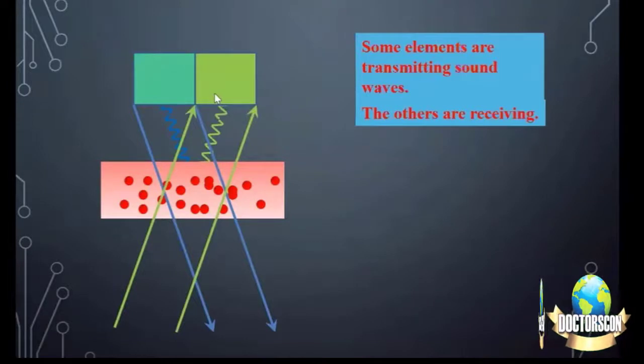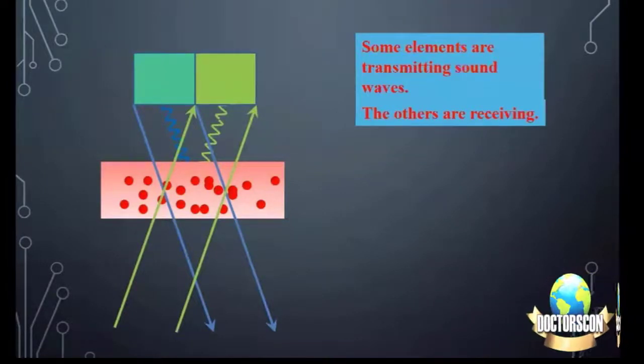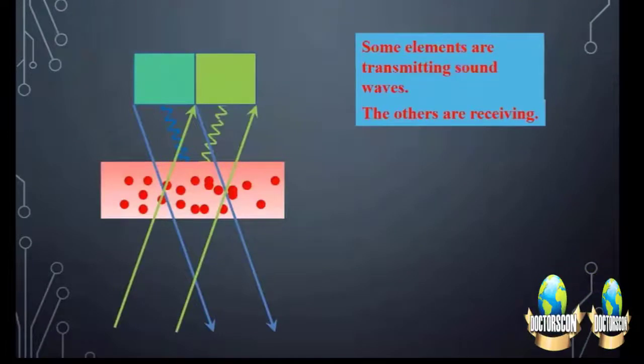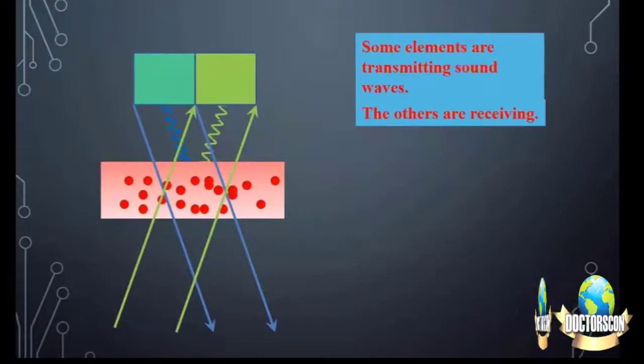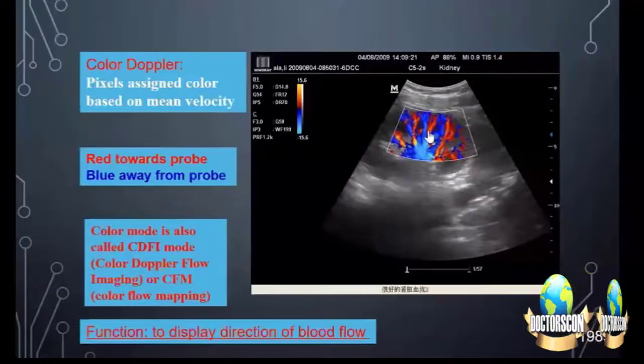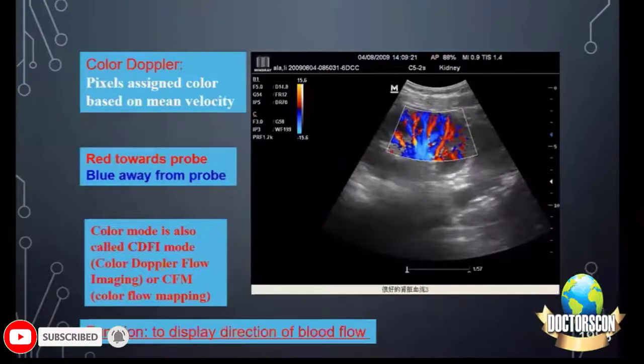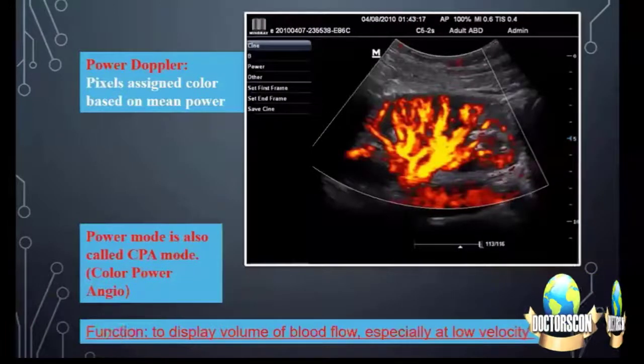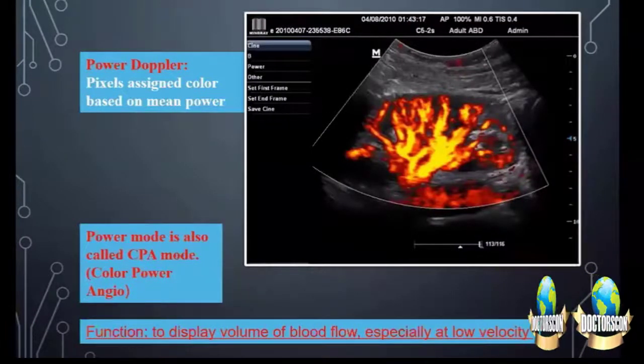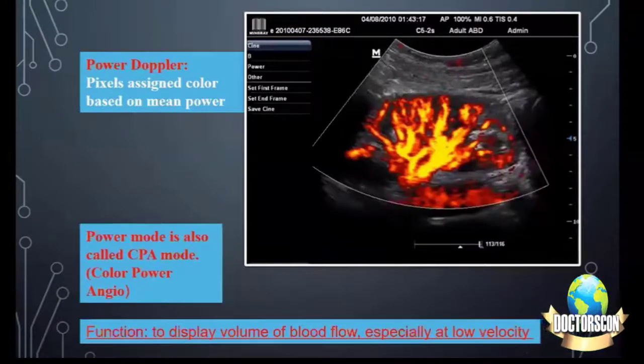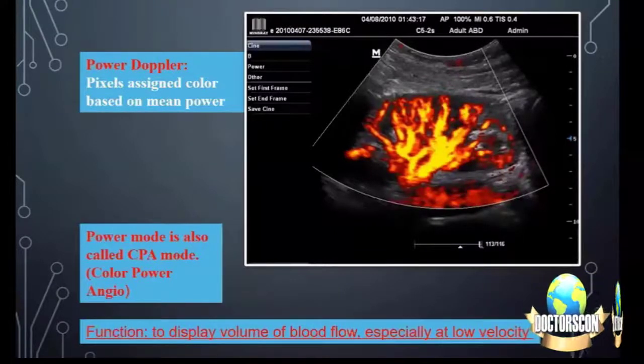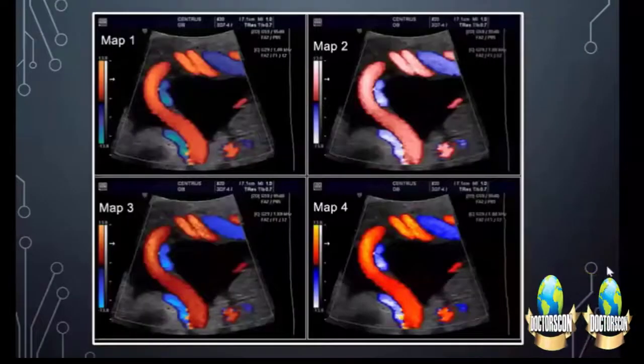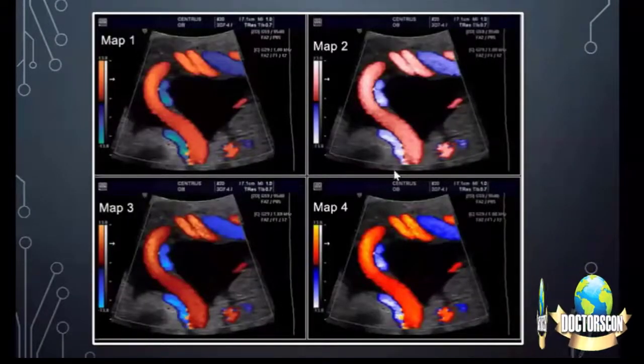Whereas in pulse Doppler, there are crystals in one housing, they send, then receive, then send and receive again. Color Doppler is based on mean velocity. As I mentioned, we can assign any color nowadays. So it detects the direction of blood flow. Then power Doppler displays the volume of blood flow, especially at low velocity, so it is more powerful. It can be directional too, and can also give us the color direction nowadays. So in directional power Doppler, we can have different maps of colors.